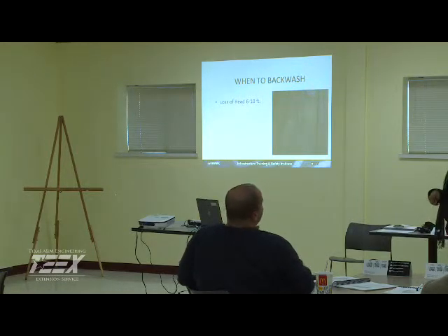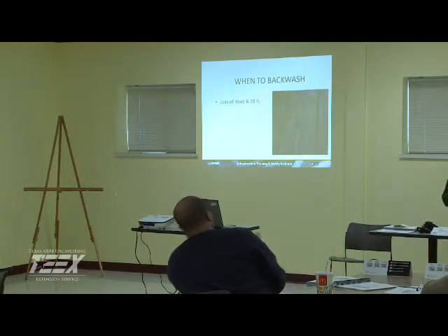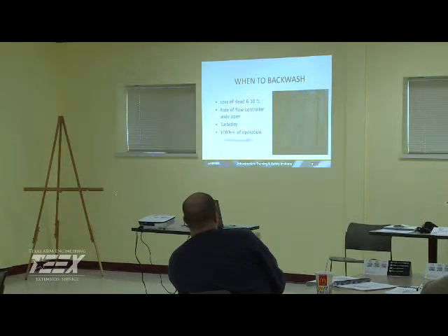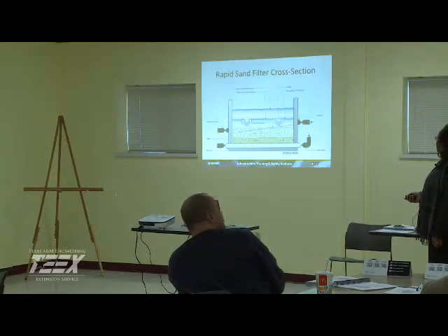All right, so we talked about yesterday backwashing because of that rule there. Again, I think Bill mentioned when there's a head loss of 6 to 10 feet and the rate of flow controller is wide open if you have turbidity issues. Or again, based on your manufacturer's recommendation, 100 hours of operation, it's time to do it, just as a preventative measure, or for part-time operation. This is the rapid sand filter cross section.